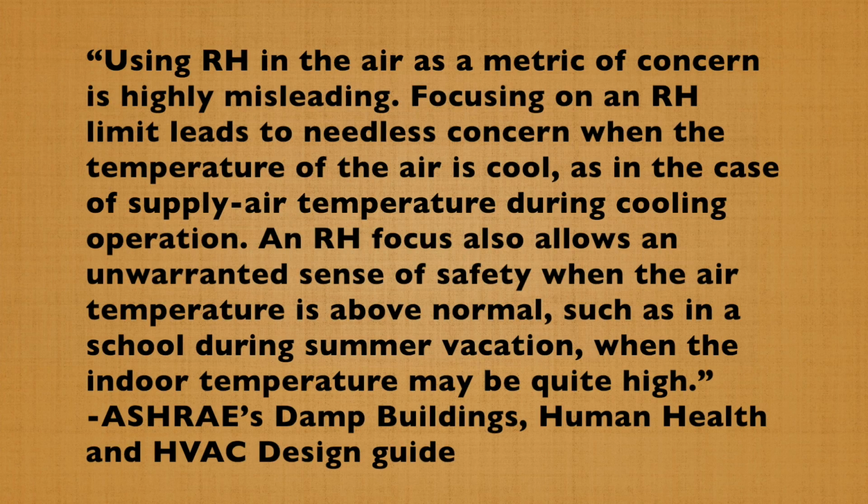To explain how RH is misleading in real-world situations, I'll read a quote from ASHRAE's Damp Buildings, Human Health, and HVAC Design Guide. "Using RH in the air as a metric of concern is highly misleading. Focusing on an RH limit leads to needless concern when the temperature of the air is cool, as in the case of supply air temperature during cooling operation. An RH focus also allows an unwarranted sense of safety when the air temperature is above normal, such as in a school during summer vacation when the indoor temperature may be quite high." So let's stop using RH as a measure of humidity and start using dew point instead.